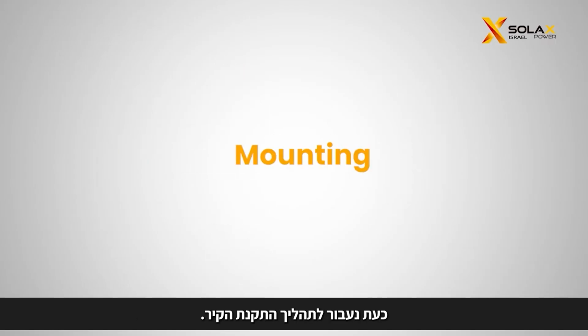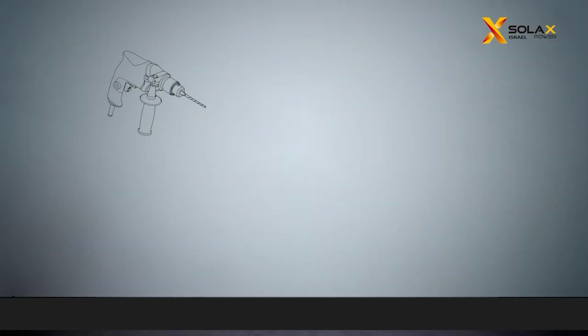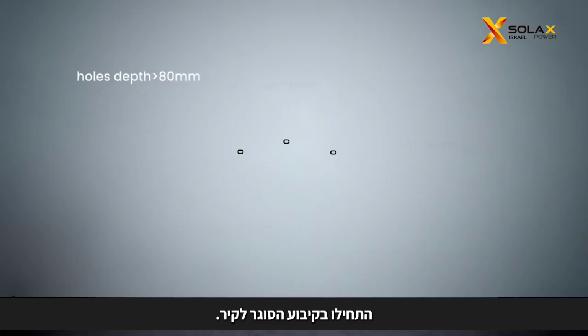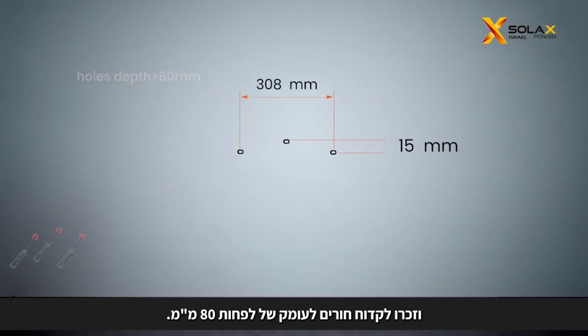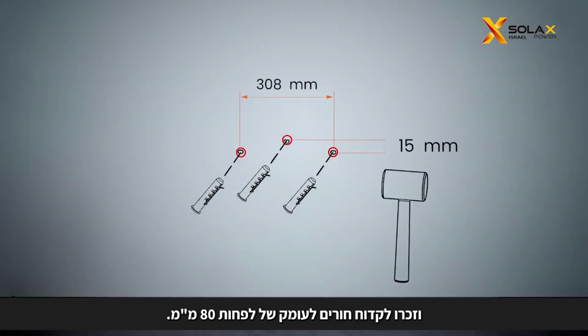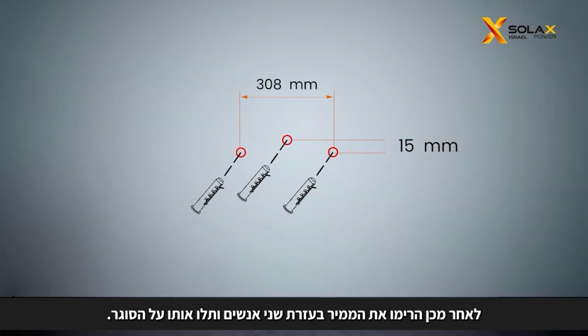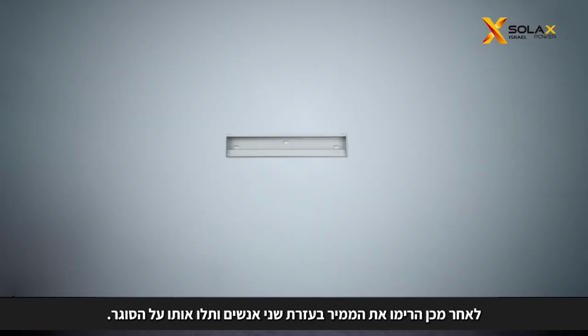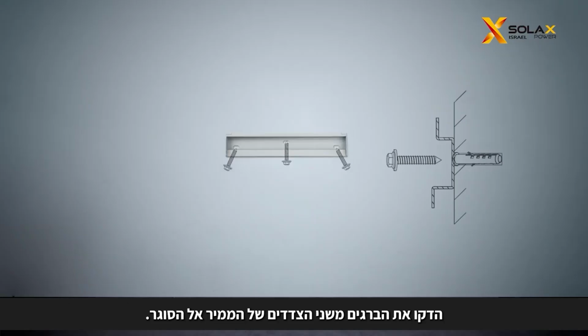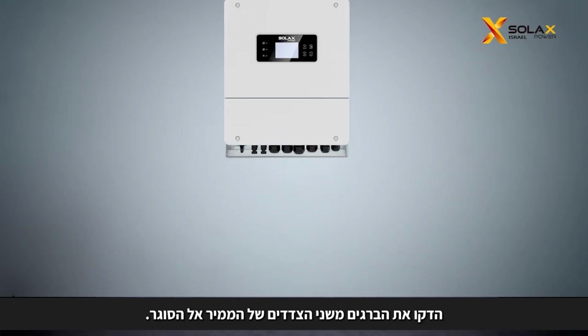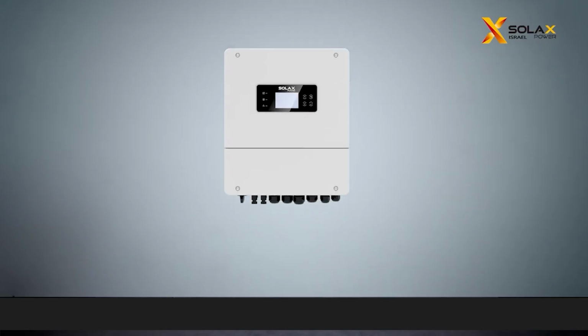Now we'll move on to the wall mounting process. Start by fixing the wall bracket to the wall, and remember to drill the holes at a minimum depth of 80 millimeters. Next, lift up the inverter with 2 persons and hang it on the wall bracket. Tighten the fixing screws on both sides of the inverter to the bracket.